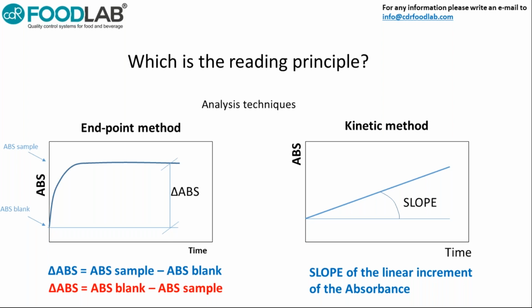Now we are going a little bit deeper into the technical detail, but this will explain how we are able to calibrate our reagents. The other is the kinetic method. In this case, we don't need to read any blank. We add the sample into the cuvette, or after the addition of the sample, we have a reagent that starts the reaction. So we keep the cuvette in the reading cell, and the analyzer reads second by second the increase of the absorbance. After 1 minute, the analyzer calculates the slope, and the slope will be our signal, and the entity of the slope will be connected to the concentration of what we are analyzing.